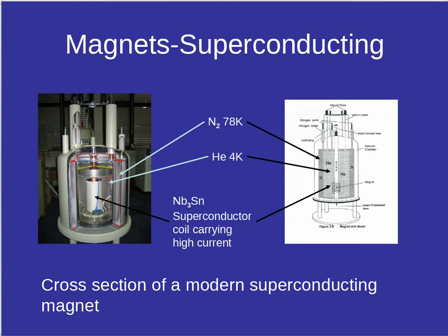Now, of course, we don't have permanent magnets as a block of ferrite anymore. What we do is we have superconducting magnets, and we've got 3 of them in our department. Here's a cutaway of what a magnet container looks like. Inside the magnet there's a great big coil of wire that can have many tens of kilometers of wire wound and wound around. That wire is a superconducting wire, and it carries a current. And if a current flows in that wire, it will generate a magnetic field.